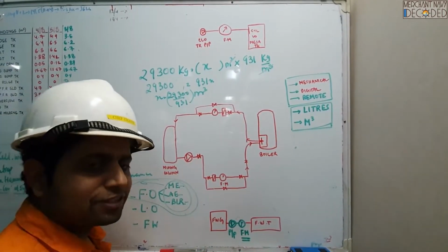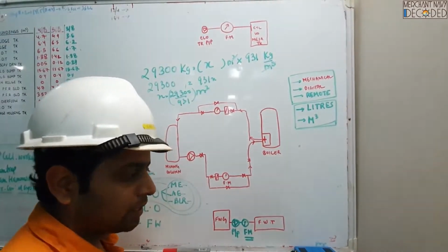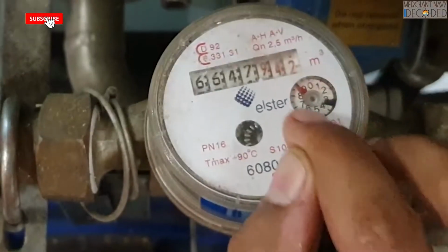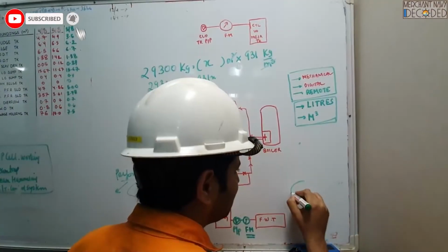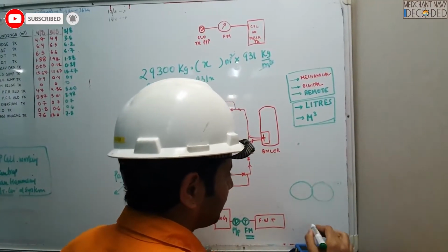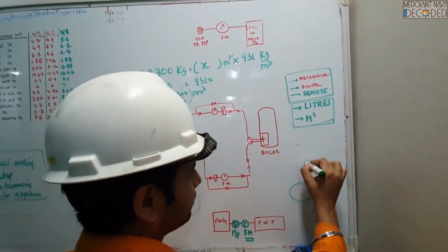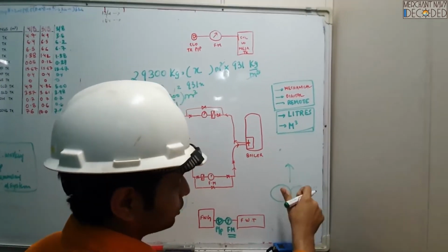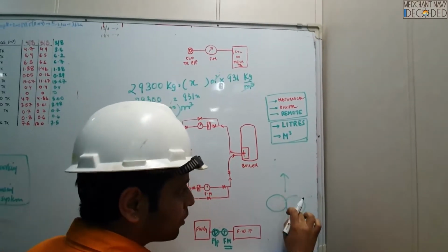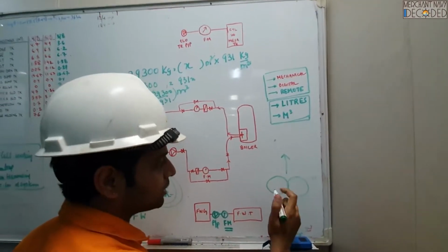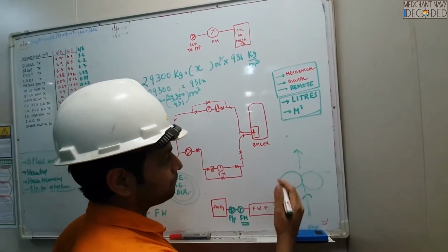Normally you have seen those flow meters fitted at home as well, where the water bill is calculated as water is flowing. So what happens, guys, is it's a gear type arrangement fitted like this. When water is coming from here, or fuel is coming from here and going over here, it is turning these gears over here. So as per a fixed amount of each turn, a fixed amount of water or fuel is flowing through these gears, and that is how it is calibrated.